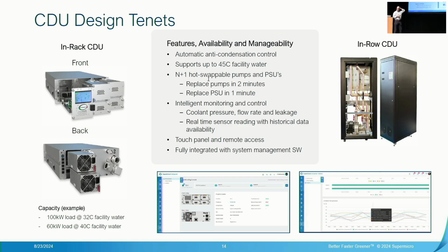If you look at the lower left, capacity -- this is one of the ones that Supermicro has that's in rack, and it can support and cool 100 kilowatts with 32C facility water. But if you have much warmer water, it's still going to work fine, it just doesn't have as much capacity inside.